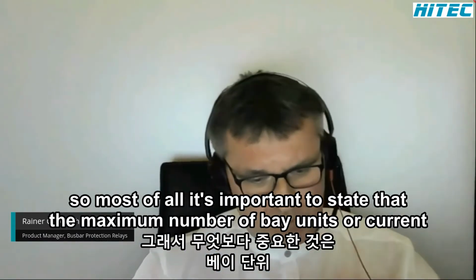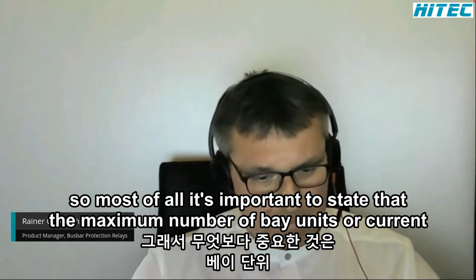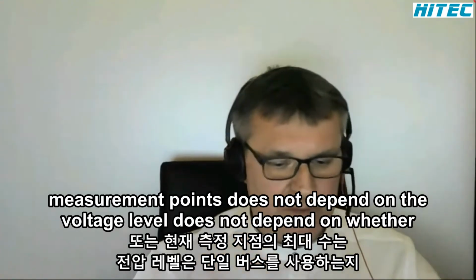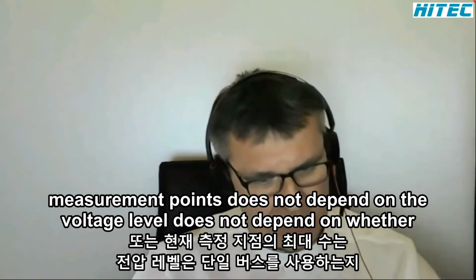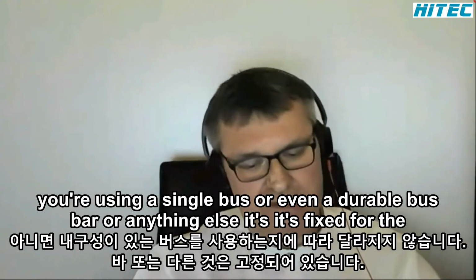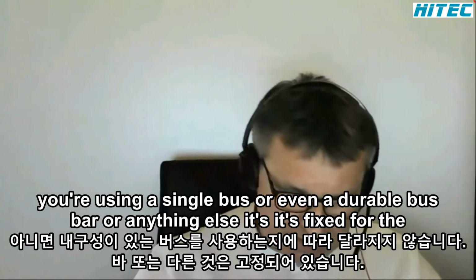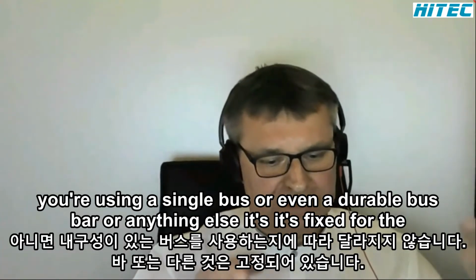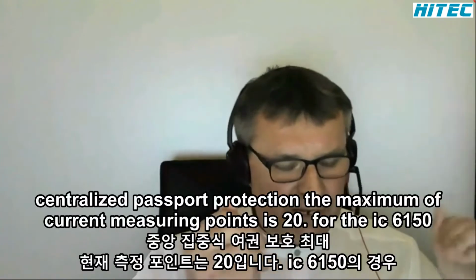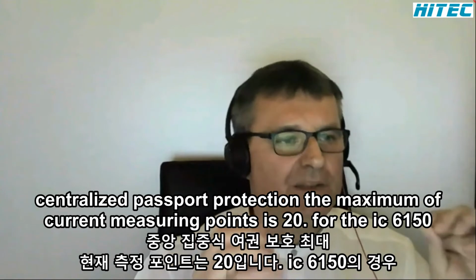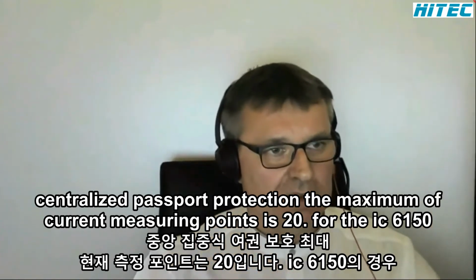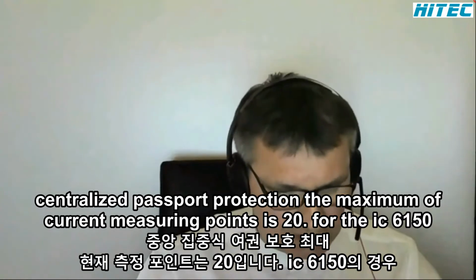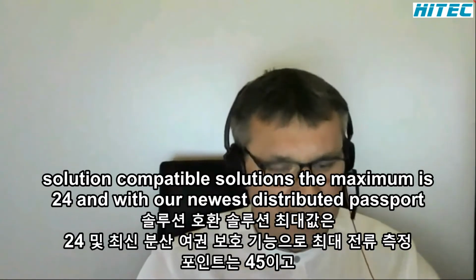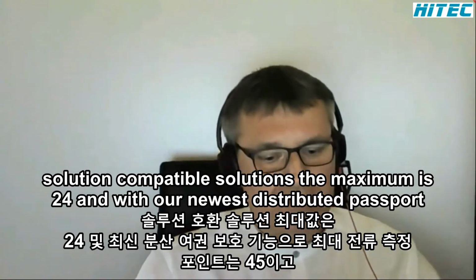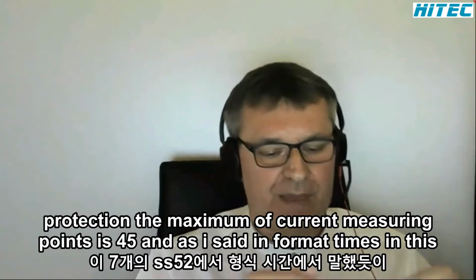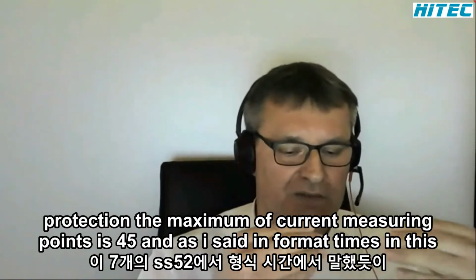Most of all, it's important to state that the maximum number of bay units or current measuring points does not depend on the voltage level, and does not depend on whether you're using a single busbar or even a triple busbar or anything else. It's fixed for the centralized busbar protection. The maximum of current measuring points is 20. For the IEC 61850 compatible solutions, the maximum is 24. And with our newest distributed busbar protection, the maximum of current measuring points is 45.